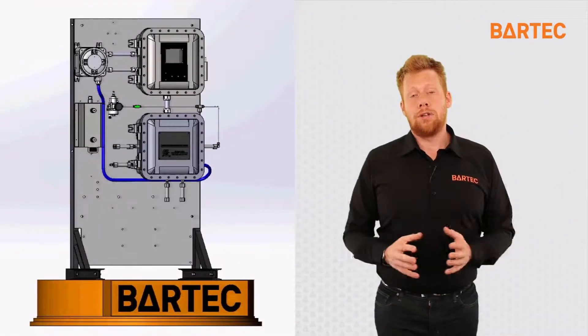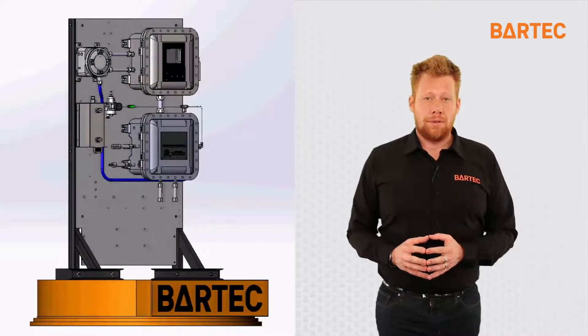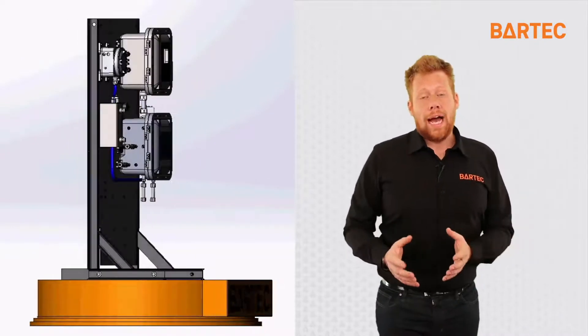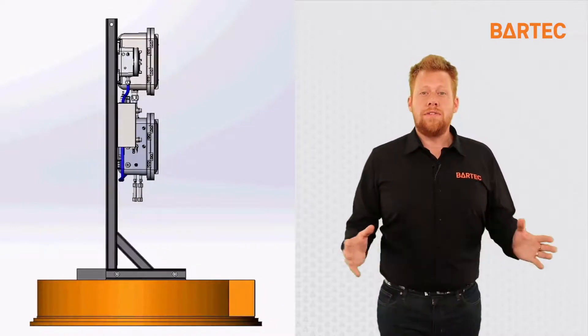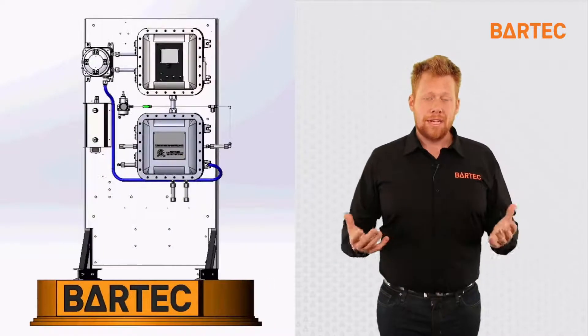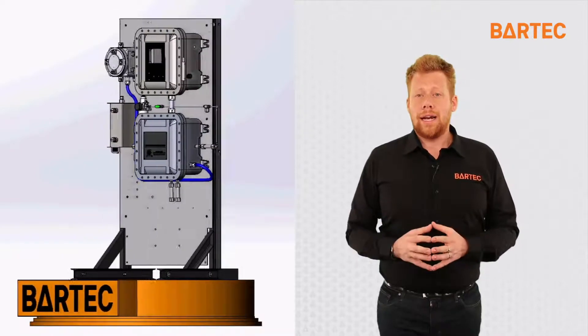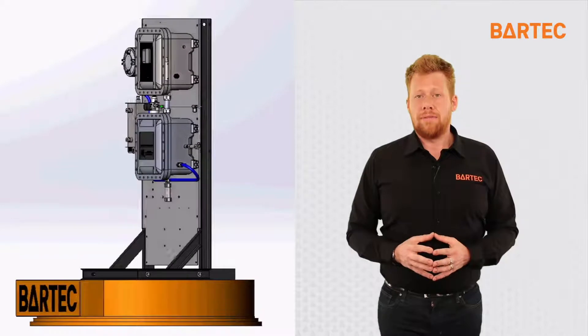The P700 weighs about 500 pounds, including the stand. The total dimensions of the analyzer is about 3 feet wide by 6 feet tall. In the following animation, we will go over how the analyzer actually makes the RVP measurement.